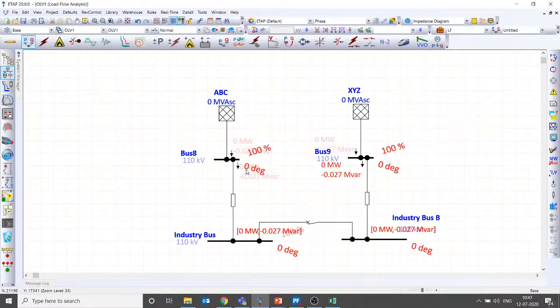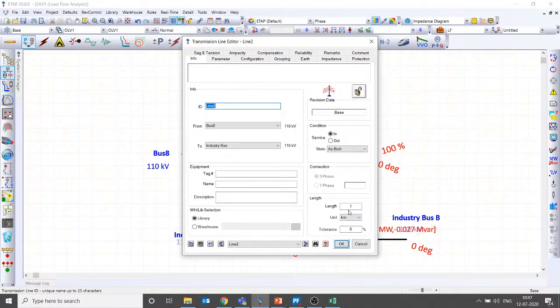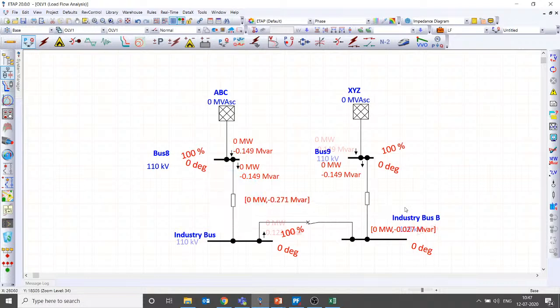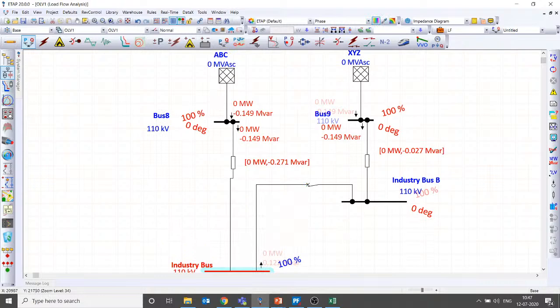Right, here the power flow is now very small. It is 100, angle 0, and this 0.027 MVAr is because of this line length of 1 kilometer. Perfect. If it is 10 kilometer, then the reactive power will be slightly more. And now you can see there is a reactive power already started flowing in your branch, right?